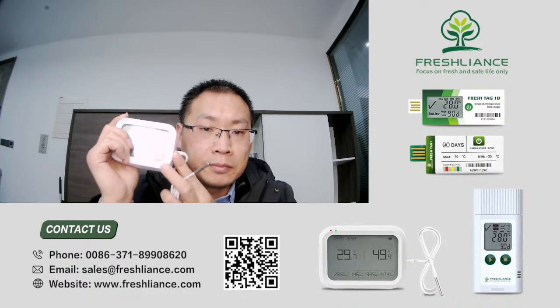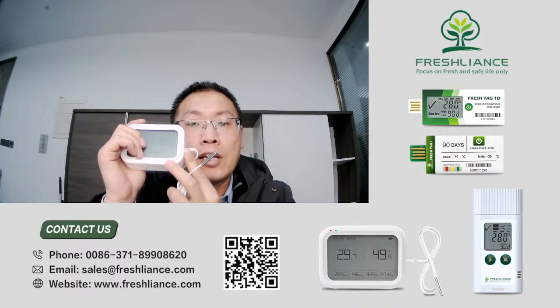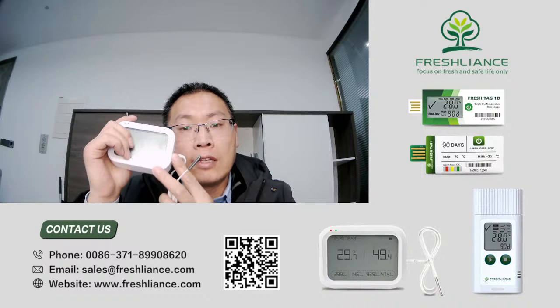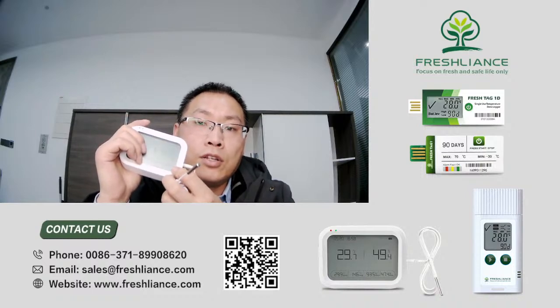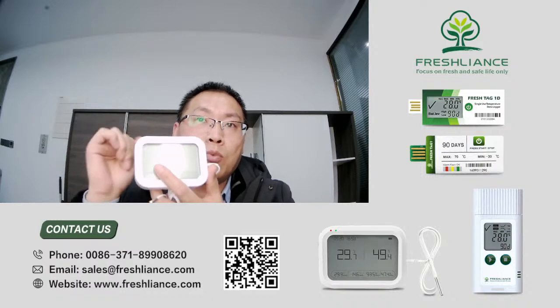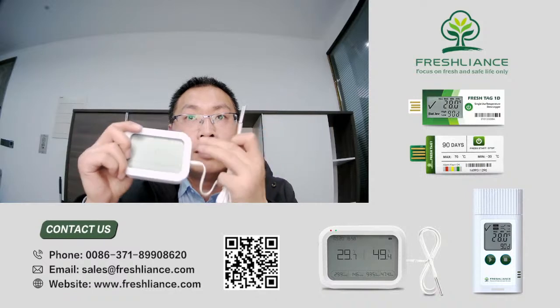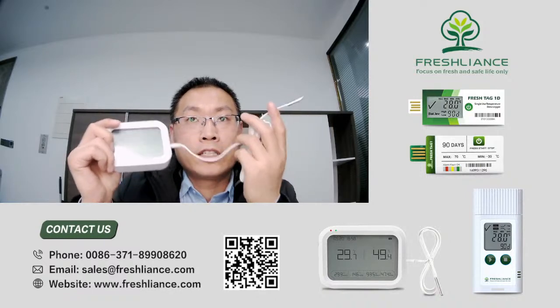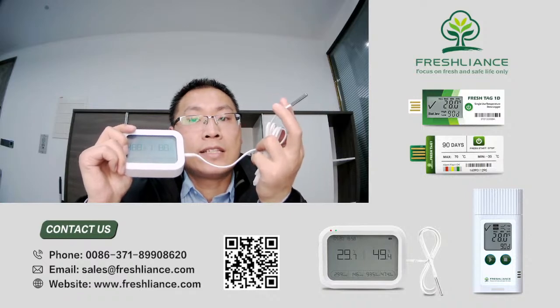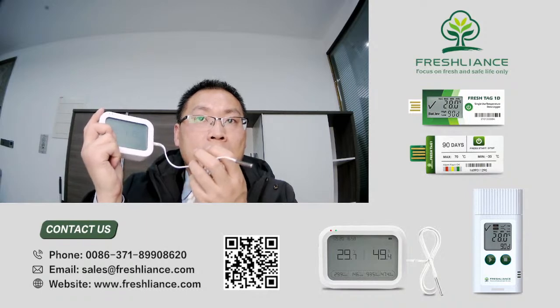Then you can make recordings for ultra-low temperatures, such as cold storage and cold chain transportation, such as the dry ice storage environment. Since the temperature will be very low, most devices will not work in that environment. So we need data loggers with external probes with cables. We just put the cable and probe inside the dry ice storage environment, and the device stays outside the environment to make the monitoring.